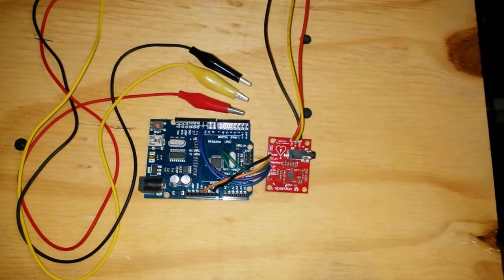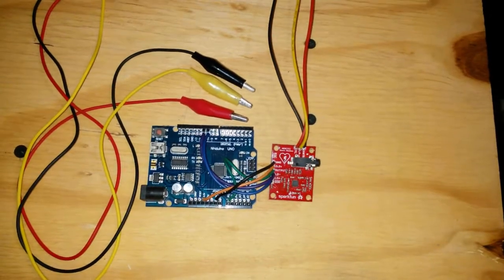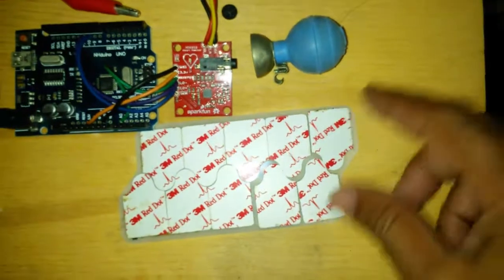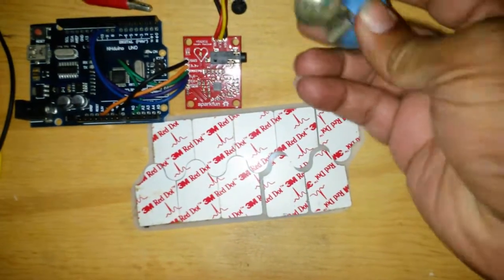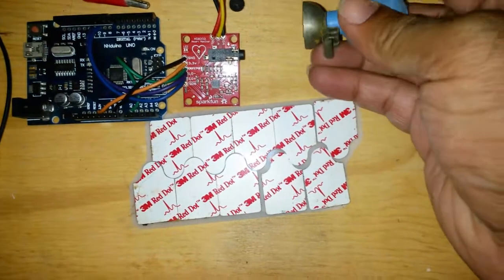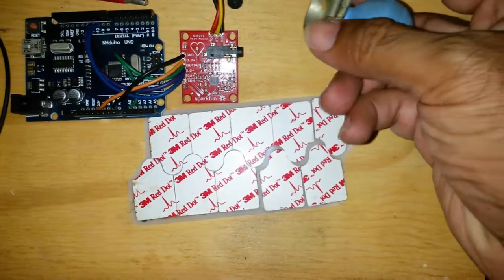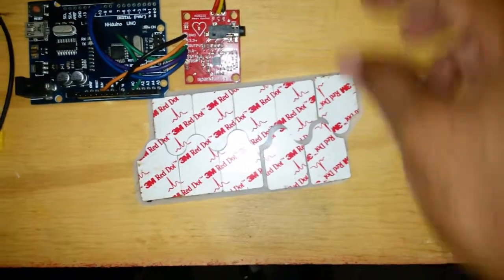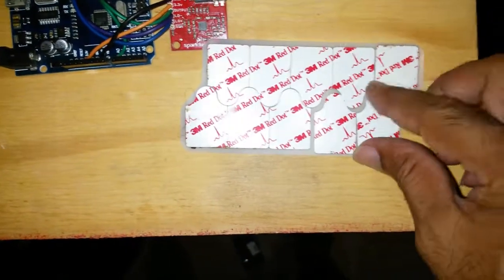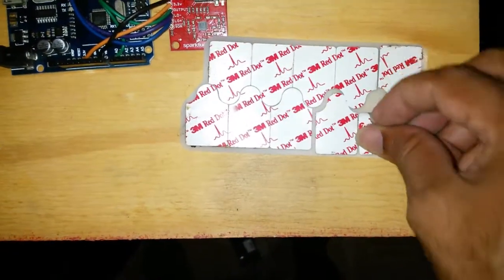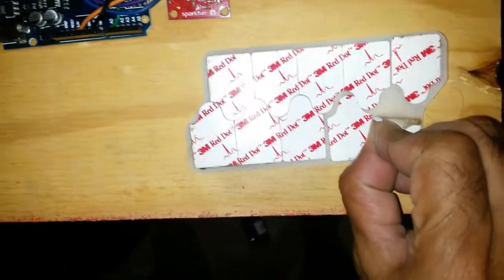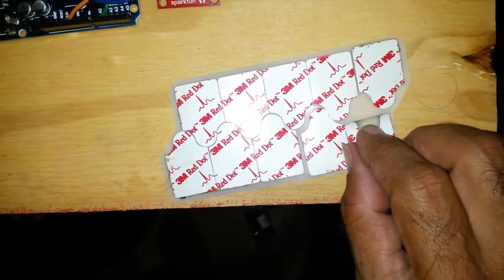And probably grab one of the press-on, suction-type contacts, and show what that looks like. Quickly, this is a suction-type contact. You press this, and there's a ball here, and it creates a suction, stays on the skin. It needs some gel, and you clip onto here. So that's not too bad. This is a stick-on type contact. If you look on the other side, these things are basically sticky gel-type things. The glue is starting to fail on this one, but yes.